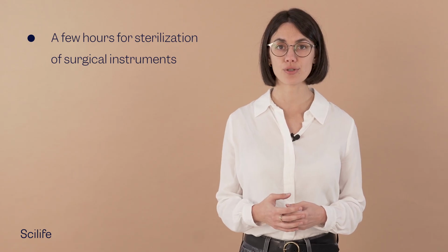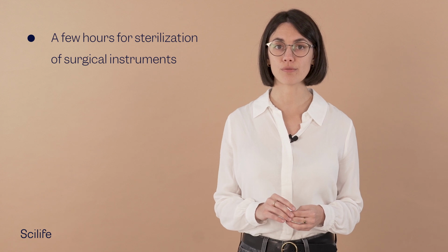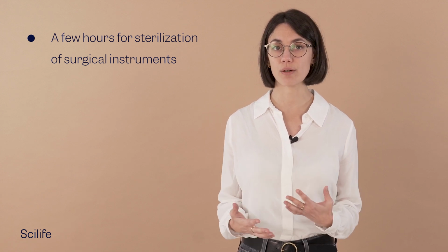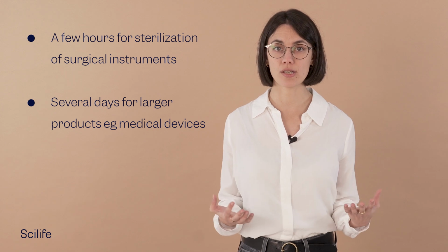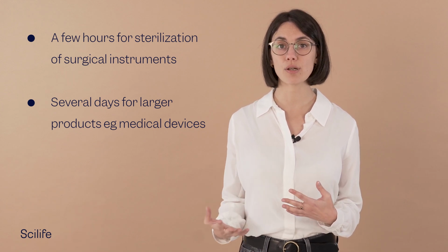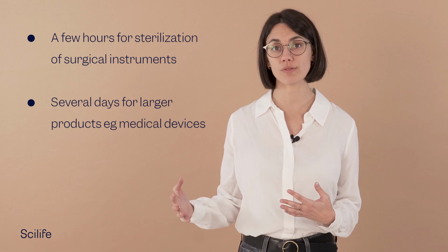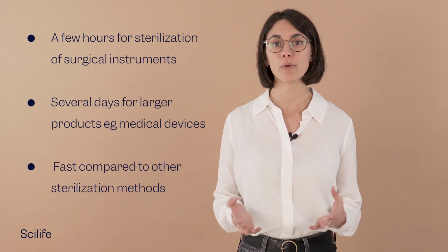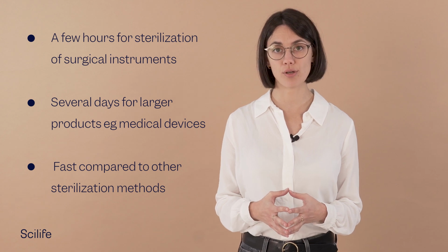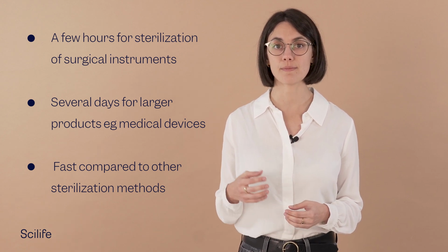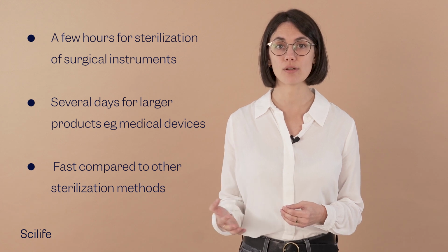The turnaround time for gamma radiation sterilization depends on the product, the absorbed dose of radiation, the type, and the size of the product. The sterilization of surgical instruments requires a lower absorbed dose of radiation and can have a turnaround time of a few hours. The sterilization of larger products, such as medical devices, may require a higher absorbed dose of radiation and have a longer turnaround time of several days. Overall, gamma radiation sterilization is a relatively fast process compared to other sterilization methods, such as heat sterilization, which can take several hours or even days. And it's a relatively safe and effective method for sterilizing a wide range of products.